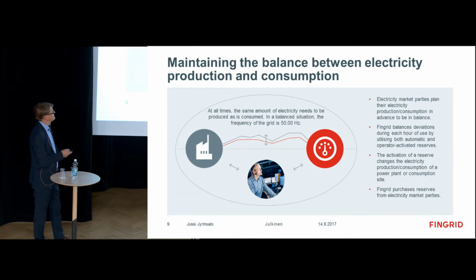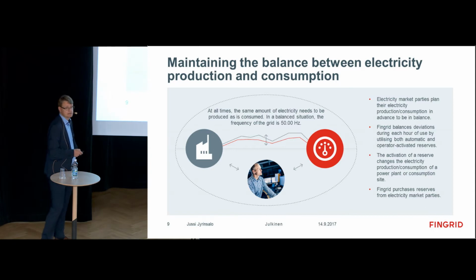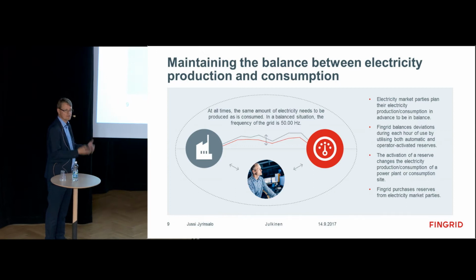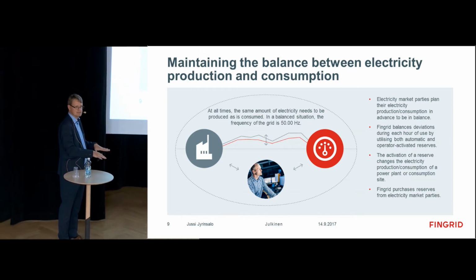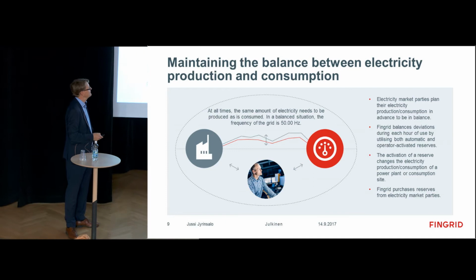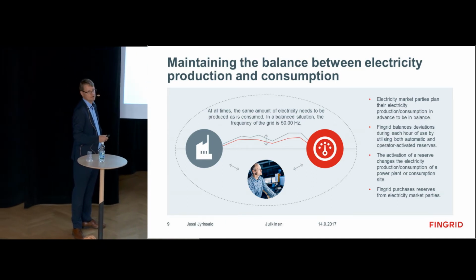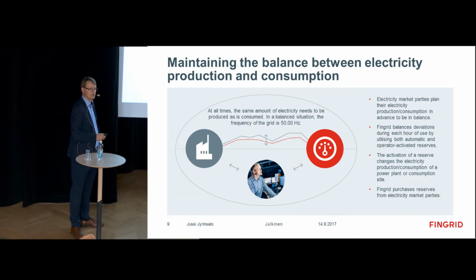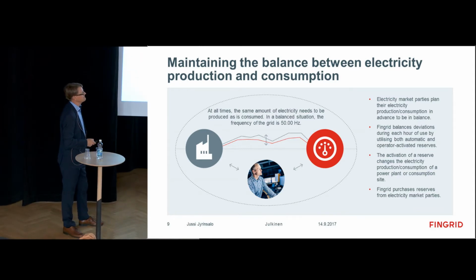Now, something about the frequency of the grid. Frequency indicates whether there is a balance between production and consumption. If there is too much consumption in your system, the frequency goes down - you have too much load on the generating machines, the synchronous machines, and they start to decelerate. Vice versa, if you have too much generation compared to the load, the frequency goes up.